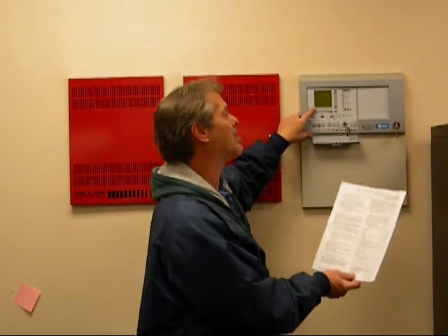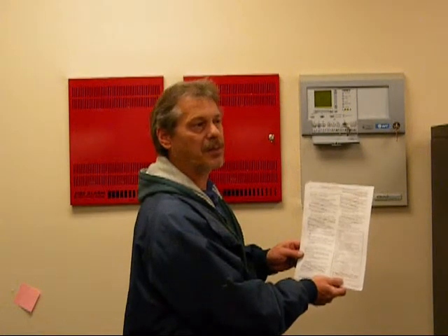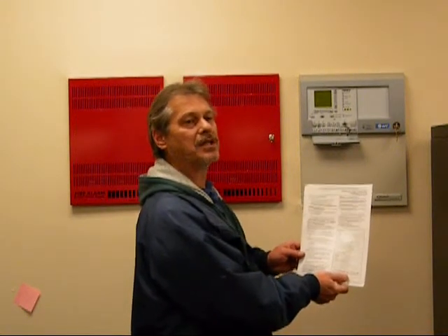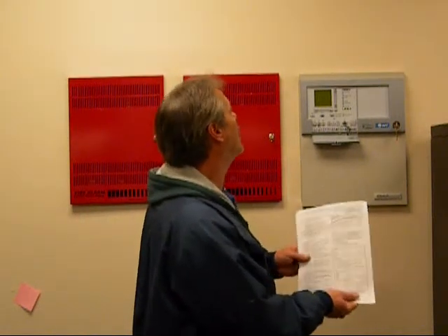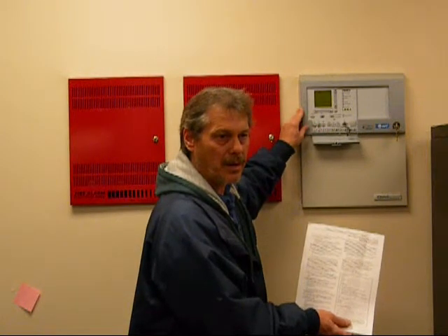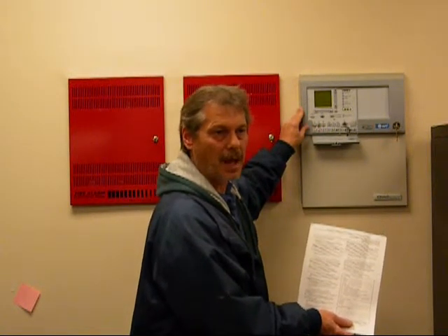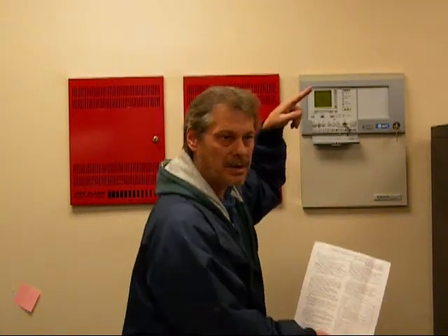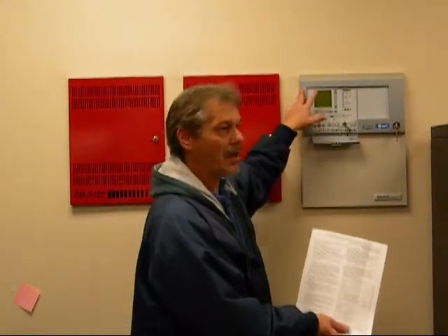The highest condition signal is an alarm condition, a fire alarm condition. Second highest would be a supervisory condition. And the lowest basically would be a trouble condition. A supervisory condition consists of a signal basically generating annunciation at the display, which means it's going to beep at the keypad. It's not going to set off your audio-visual devices, your horn strobes in the hallways. Okay, it's not going to evacuate the building. Okay, but regardless of the signals, they're all going to be displayed at this panel.